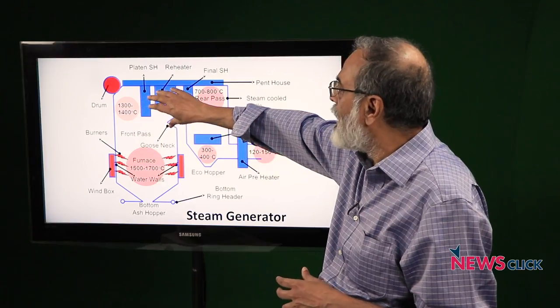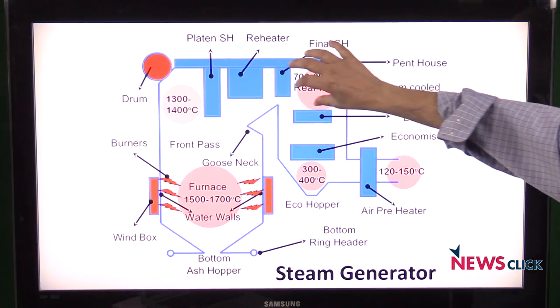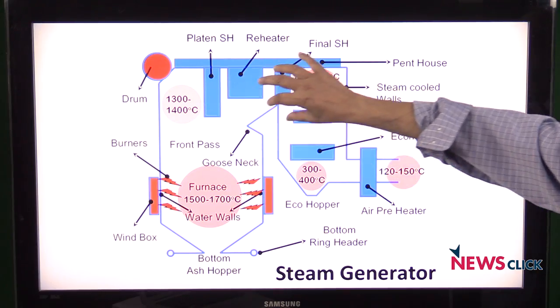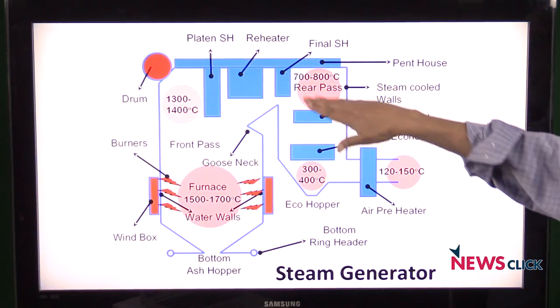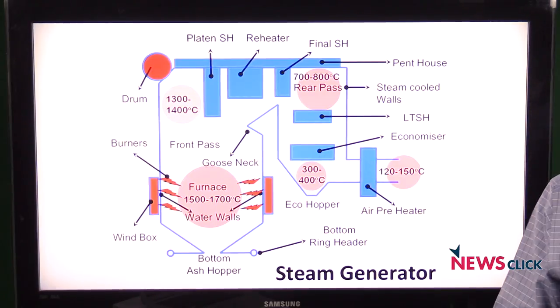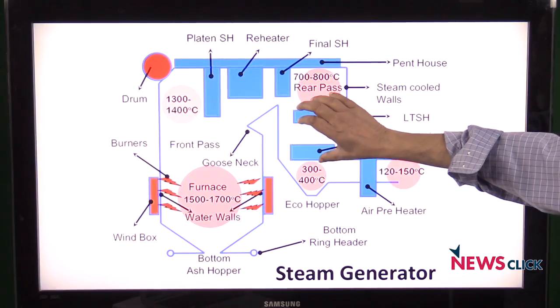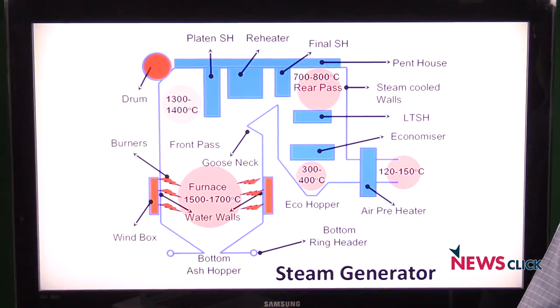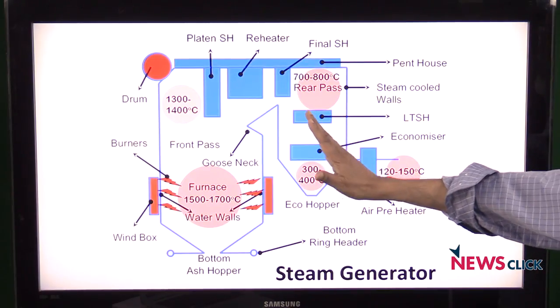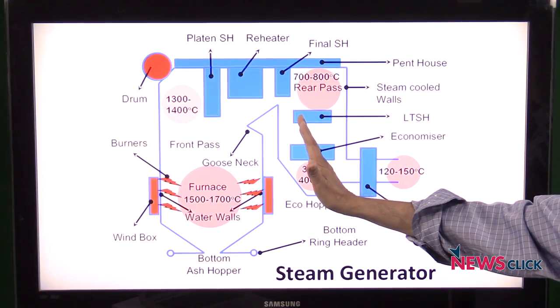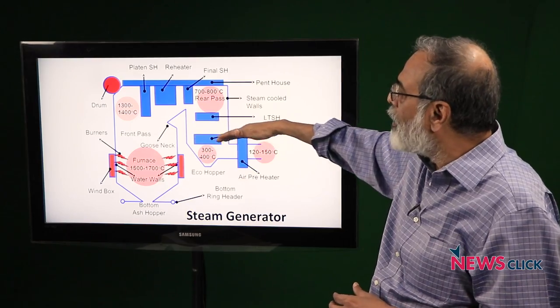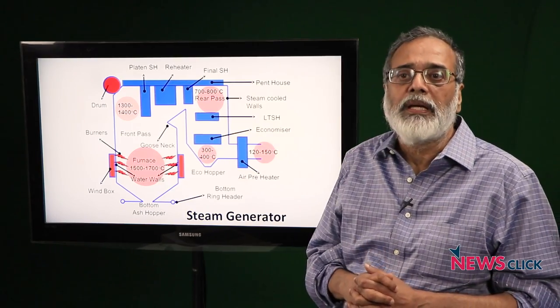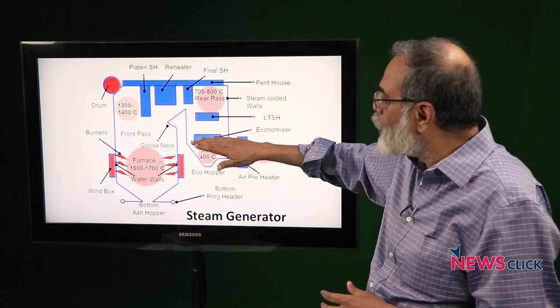The second part that happened was that a lot of unfired fuel was getting carried over into what is called the second pass. Once this lot of unfired coal particles were carried over, they caught fire and there was an explosion here, which led to the economizer flue gas escaping into the atmosphere.